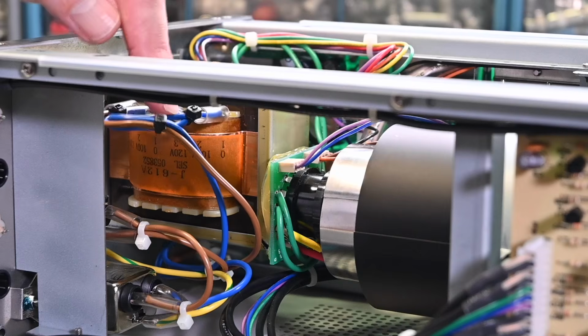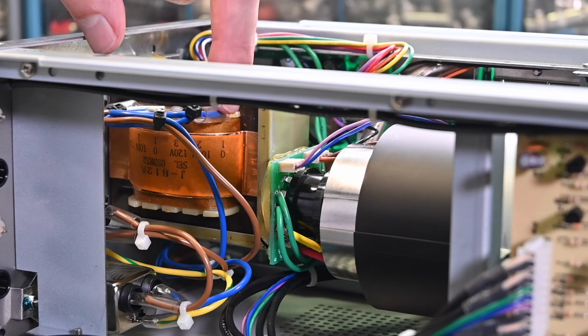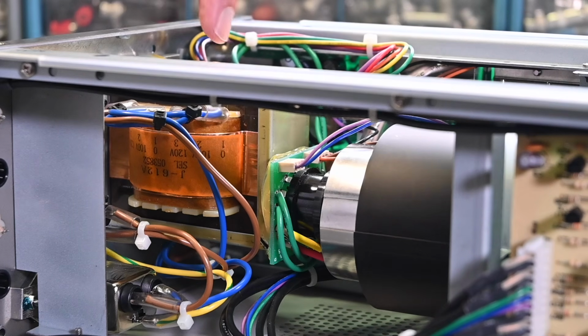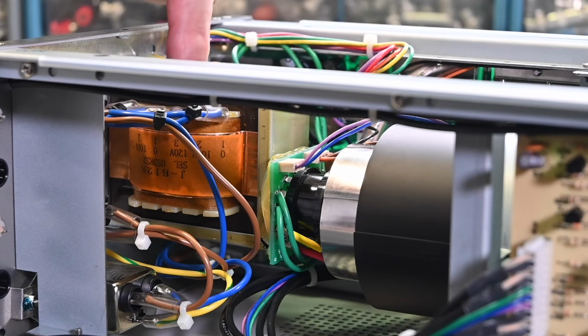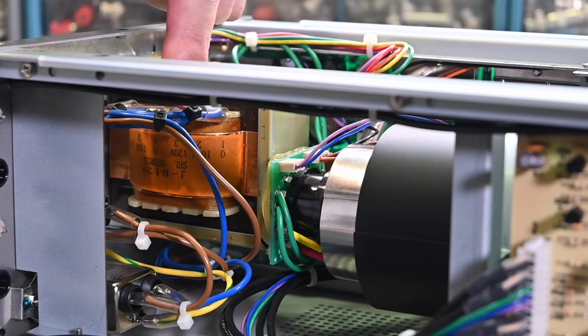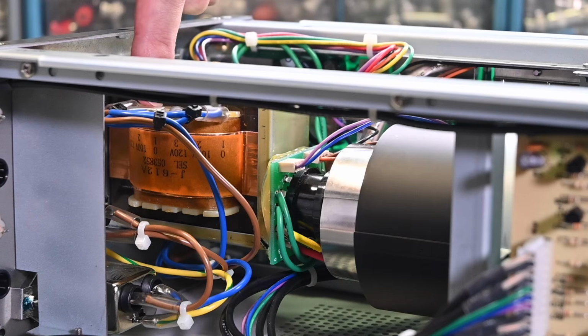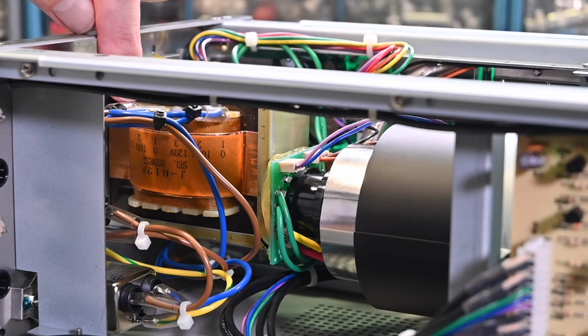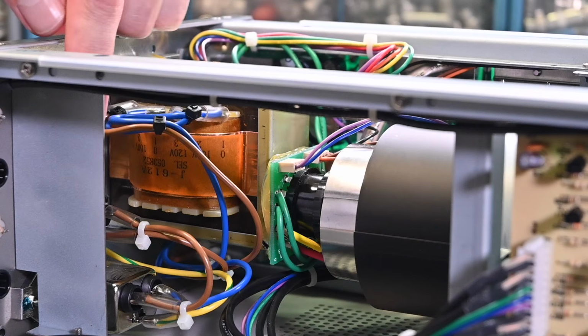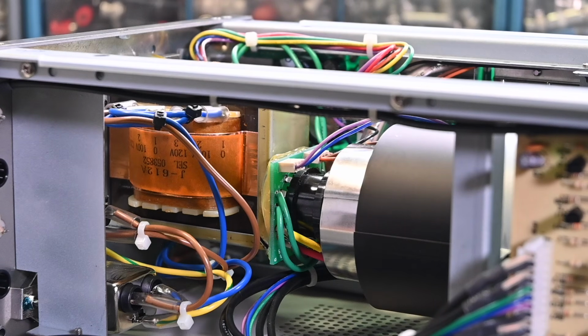So it's over here on this blue wire, and that's going to this tap, which is 0, so the bottom end of the winding. And then the 120 volt tap on this first winding is going right over here to the bottom end of the next winding. So they are in series. And then the far end over here, 120, is the brown wire, and then that's returning back, that's on the AC line. So yes, this, being in series means that it is set up for the 240 volts, so it must have left the factory this way.